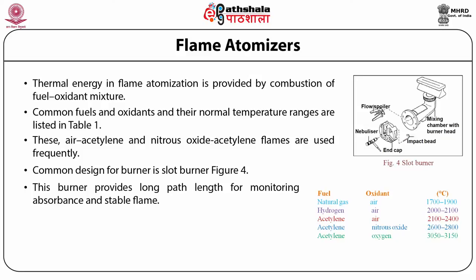The burner is mounted on an adjustable stage that allows the entire burner assembly to move horizontally and vertically. Horizontal adjustment is necessary to ensure that the flame is aligned with the instrument's optical path. Vertical adjustments are needed to adjust the height within the flame from which absorbance is monitored. This is important because two competing processes affect the concentration of free atoms in the flame.